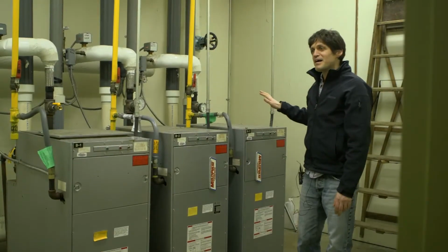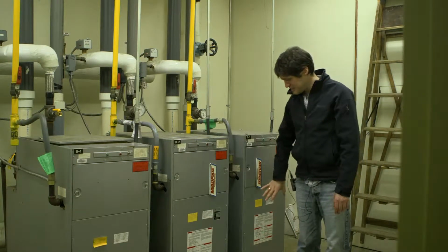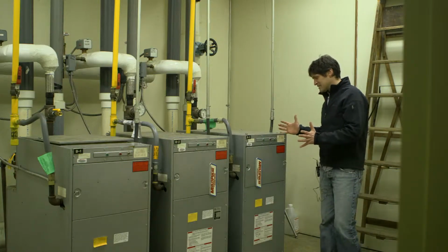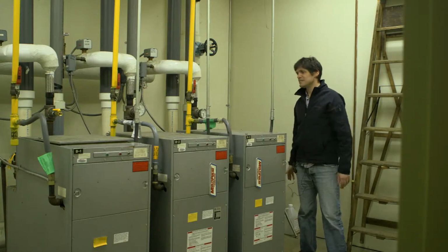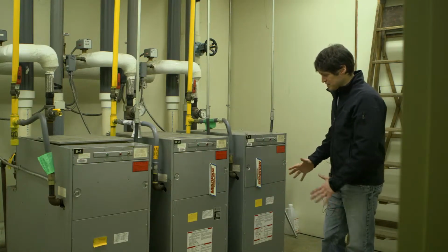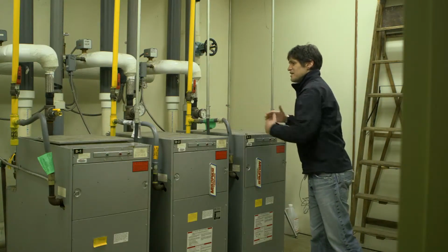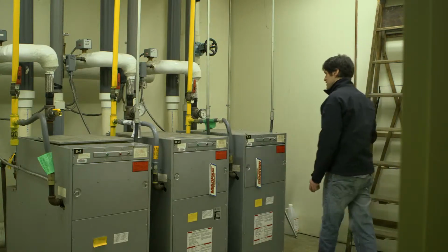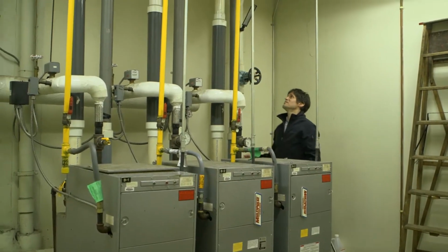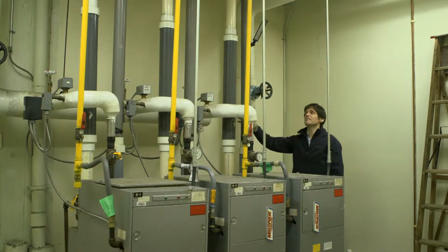These are three forced draft boilers. We can't really see the burner because they're completely packaged in the boiler case. But inside, what we typically see for forced draft boilers is the burner sitting a little bit in front of the heat exchanger itself, and we can see that we have two plastic pipes leading to the boiler. One of them is used as combustion air from the outside.